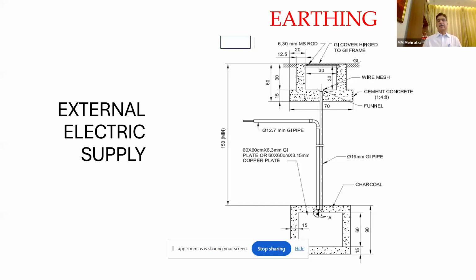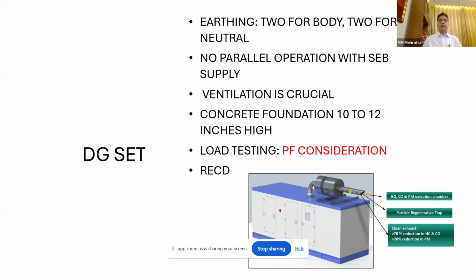Earthing wire, as I have told, will be half the size of the main conductor, with a minimum size of 1.5 square mm as given in the IS codes. Now, DG set, you have seen that in the previous photograph. Earthing, I mentioned, there are two kinds of things where earthing is used. One is machine, the other is the supply system.